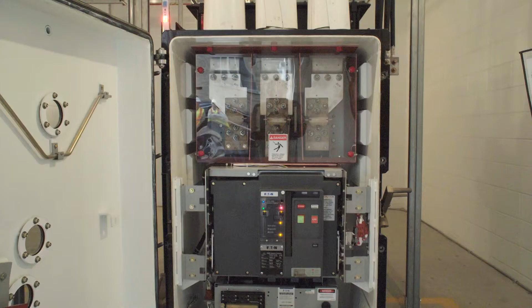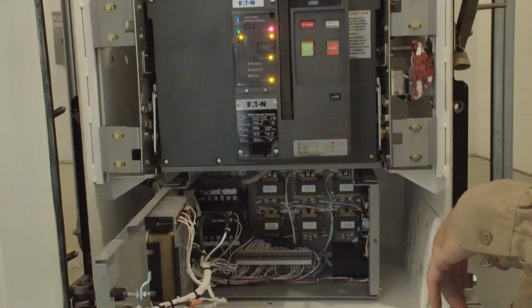It's an arc indicating module that looks at the current coming and going, and it can operate at 2.5 times faster than the CT rating of this breaker. And you couple that with the speed at which this breaker opens, basically clearing the event in 60 milliseconds. Put that in perspective, it takes 300 to 400 milliseconds to blink. So it takes it from a category 4 to a category 1.